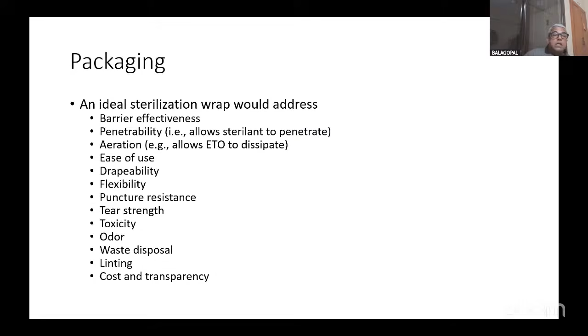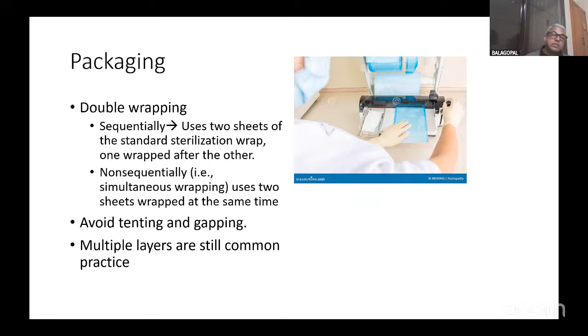The ideal sterilization material should have the following qualities. And for packaging, you can have either double wrapping, which can be sequential or non-sequential. Sequential uses two sheets of wrapper separately. In the non-sequential method, wrapping is simultaneous using two sheets, which reduces the time.